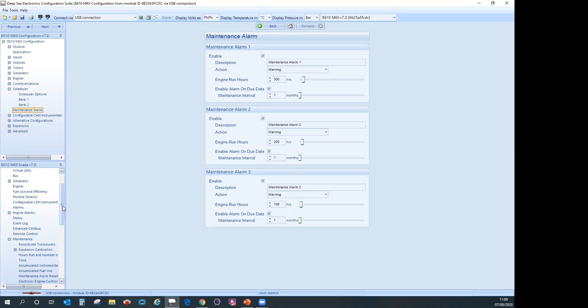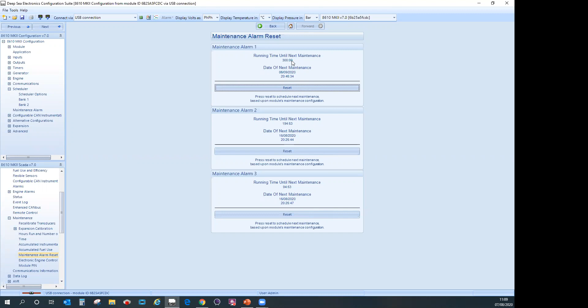You can do this from the front panel, or you can turn that feature off and insist that it has to be done from a laptop. And that's quite common because it means that for the guy on site, there's no temptation to just go and press the stop button and reset the alarm. Instead, someone competent who understands what the maintenance alarm means is going to go to site, take a laptop and reset the alarm. So you just go to SCADA, maintenance alarm reset, and then press reset, and that puts the alarm back to 300 hours. Okay, it's all dependent on what you want to do. So that's what SCADA is actually for. That's another good example of SCADA.